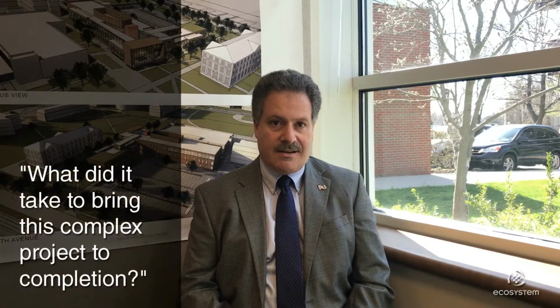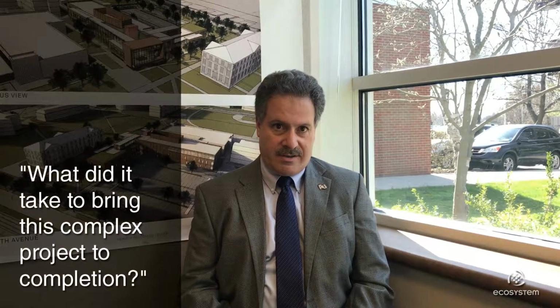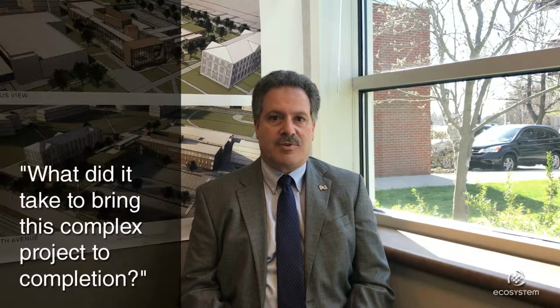The project was extremely complex. We were trying to retrofit modern equipment into a boiler room that was built in 1928. It took a lot of teamwork between the university and Ecosystem to get the project to work. We replaced 3 aging boilers, installed a brand new cogen, a 2 megawatt unit, and because it was going inside the building, we needed a sound-attenuated enclosure around it. We moved it 3 or 4 times, finally found a spot that worked, and put the whole boiler room together. The project's been running very well for the last 6 months.